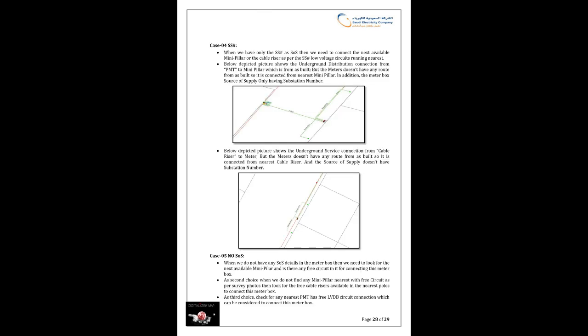Case 4: SS. When we have only the SS as SOS, then we need to connect to the next available mini pillar or the cable riser, as per the SS low voltage circuits running nearest. The picture below shows the underground distribution connection from PMT to mini pillar, which is from as-built, but the meters don't have any route from as-built, so it is connected from the nearest mini pillar.